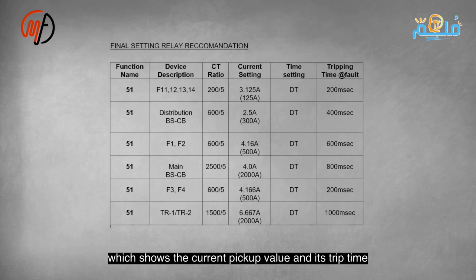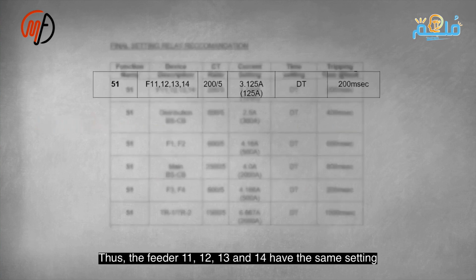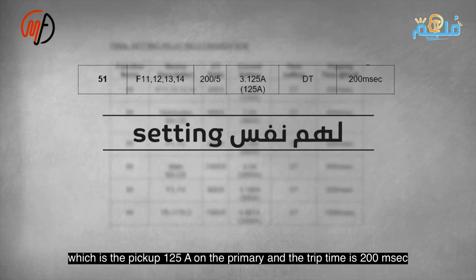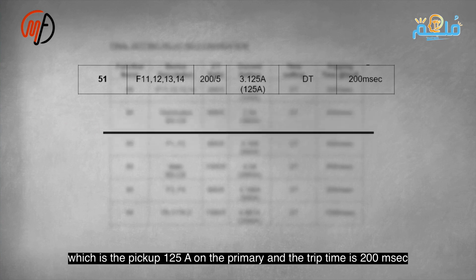Feeders 11, 12, 13 and 14 share a setting: 125 A pickup on the primary, 200 ms trip time. The bus section circuit breaker has a 300 A pickup current and 400 ms trip time. Feeders 1 and 2 also share settings: 500 A pickup, 600 ms trip time, maintaining a 200 ms gap between stages. The bus section circuit breaker has a 2000 A pickup on the primary and an 800 ms trip time.